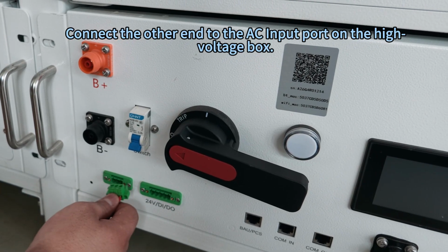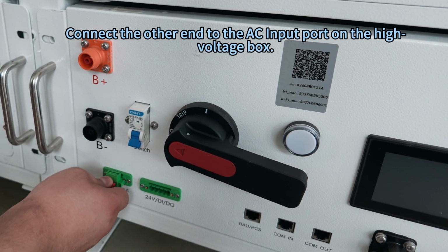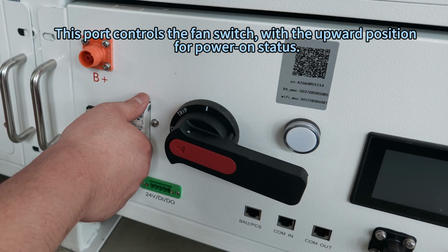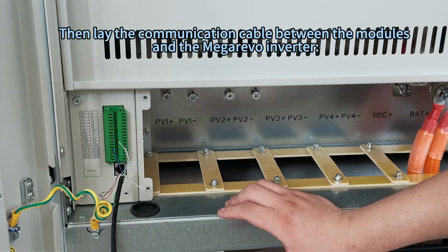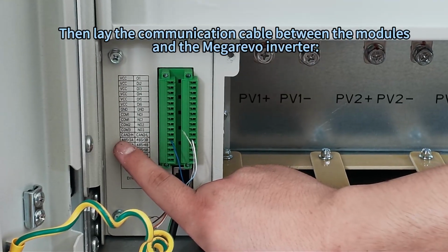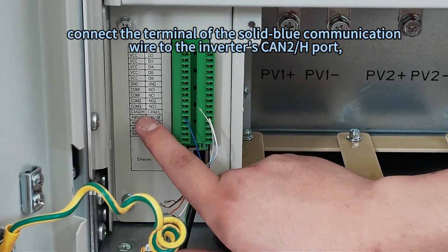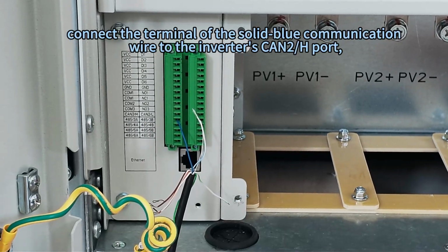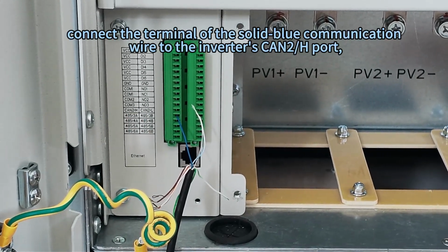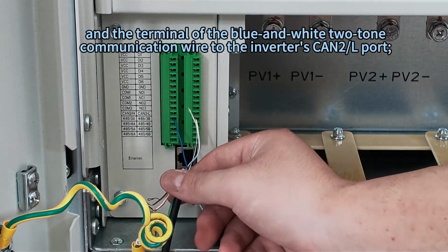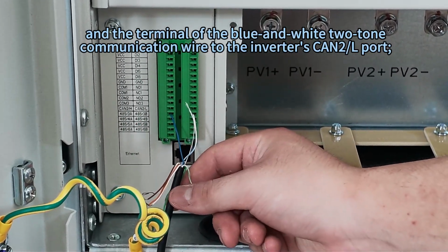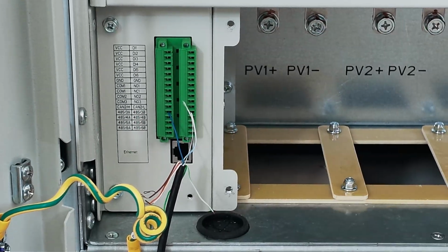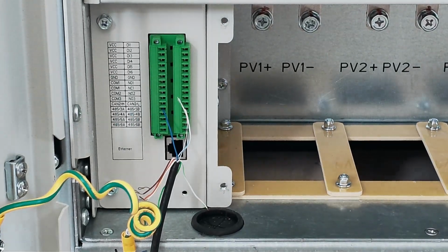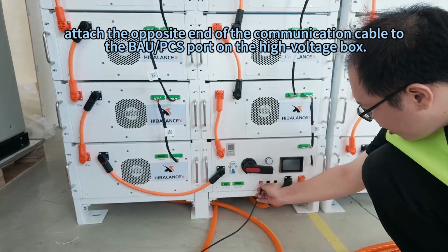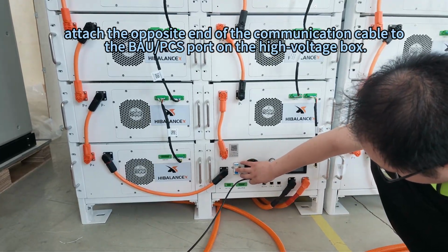Connect the other end to the AC input port on the high voltage box. This port controls the fan switch with the upward position for power on status. Then lay the communication cable between the modules and the Megarevo inverter. Connect the terminal of the solid blue communication wire to the inverter CAN2H port and the terminal of the blue and white two-tone communication wire to the inverter's CAN2/L port. Attach the opposite end of the communication cable to the BAU PCS port on the high voltage box.